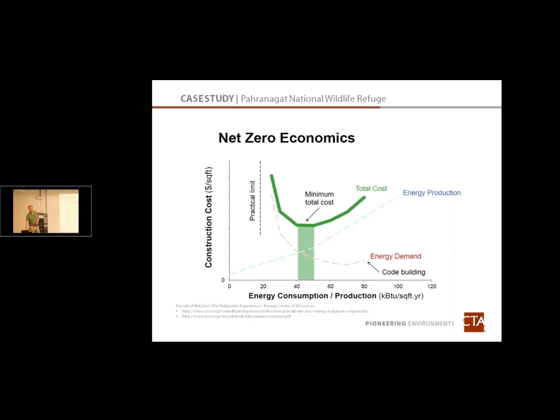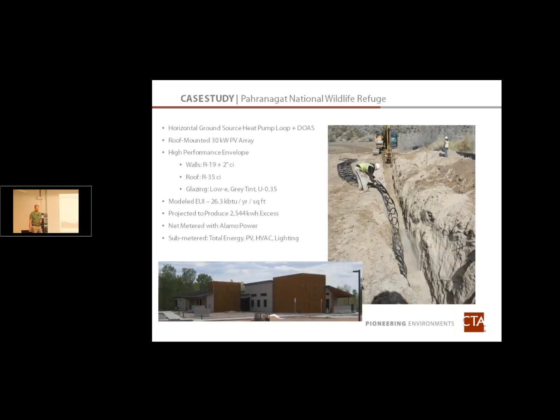Working with the contractor to figure out what was cost effective for him, being kind of 90 miles out in the middle of nowhere, we had to consider how to get things there and how they're going to be maintained. So we ended up with a small ground loop heat pump system. Essentially, the heat rejection is 10 feet underground, using plastic pipe that's good for a long time. Then you've got basically residential, light commercial heat pumps inside, and anybody from the region knows how to maintain those fairly well.